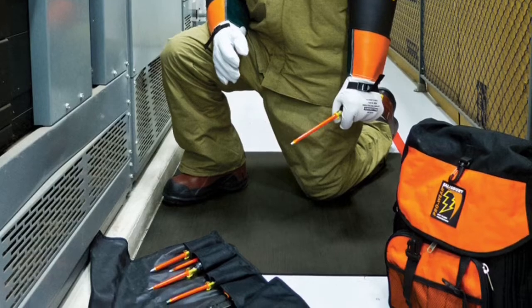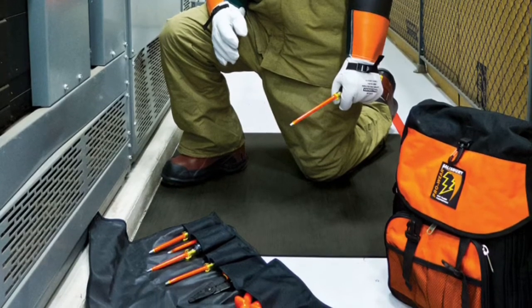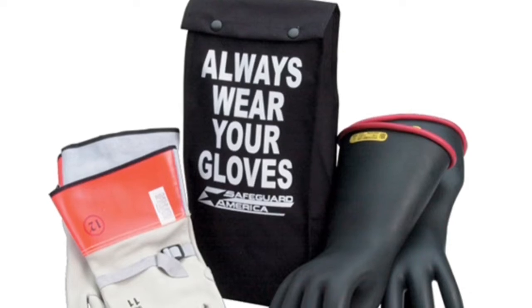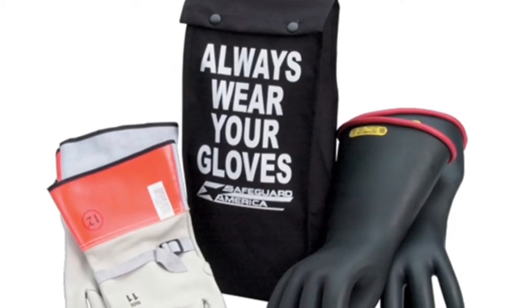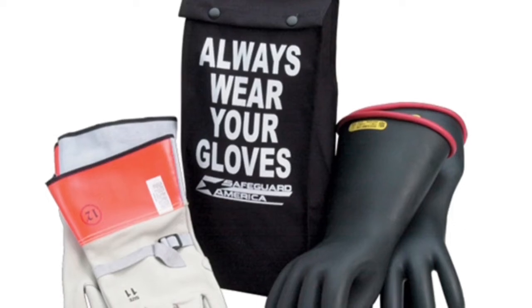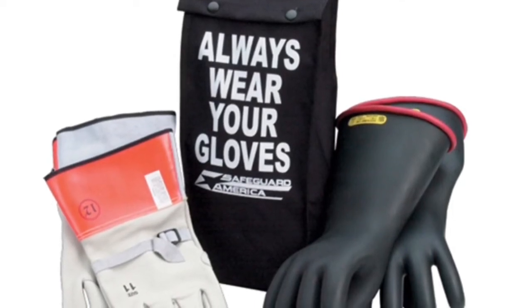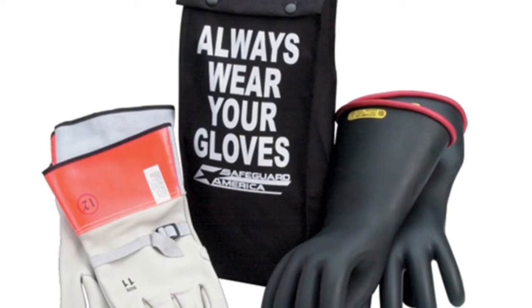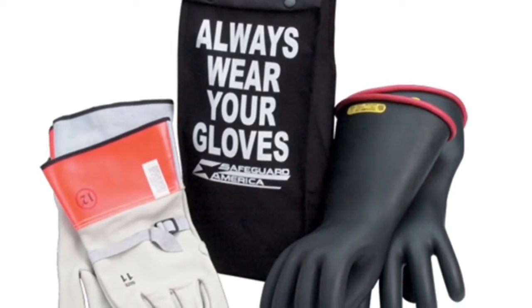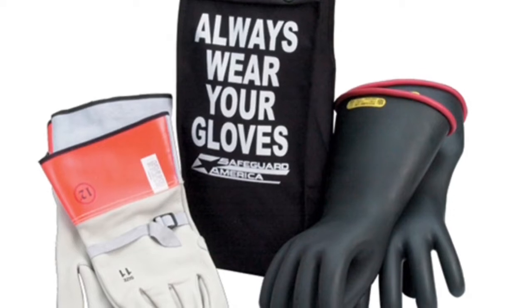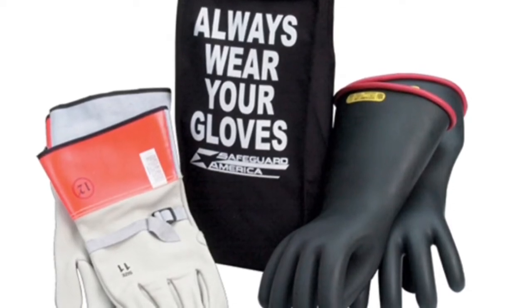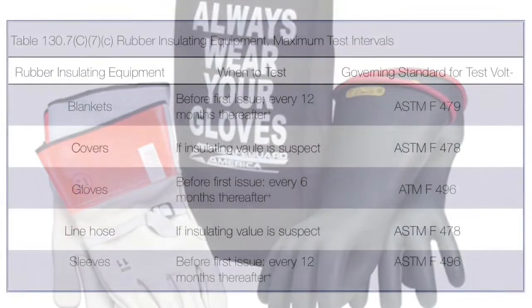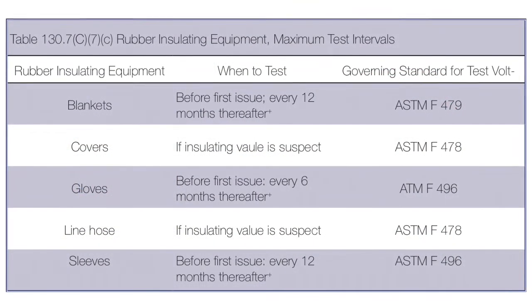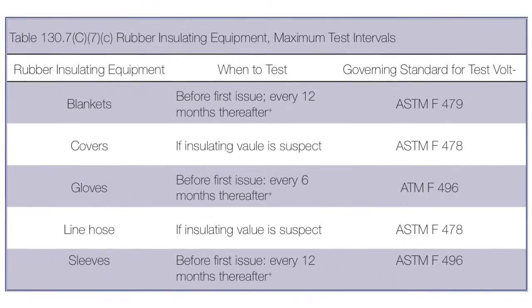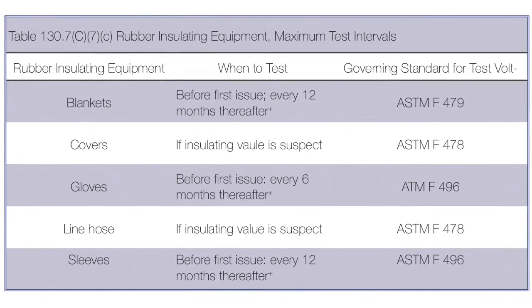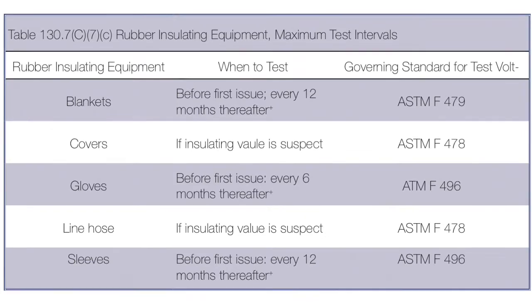Rubber insulating gloves shall be rated for the voltage for which the gloves will be exposed. Heavy-duty leather gloves or leather protectors worn over the rubber gloves are included as arc flash protection. Leather materials are typically not arc flash rated. However, heavy-duty leather gloves made entirely of leather with a minimum thickness of 0.03 inches or 1/32 of an inch that are unlined or lined with non-flammable, non-melting fabrics have been shown to have arc thermal performance values in excess of 10 calories. Table 130.7 C7 in the NFPA 70E shows maximum test intervals for rubber insulating equipment. Blankets must be tested every 12 months, gloves every 6 months, and sleeves every 12 months.